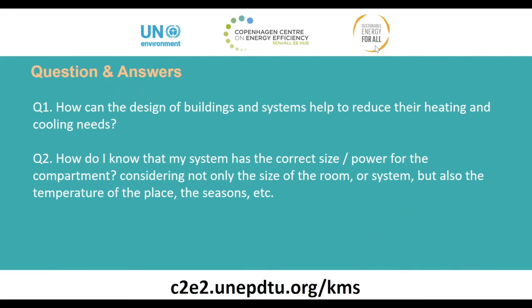Reducing or optimizing your heat loads need not necessarily be something so extreme that you have to change the designs of your buildings and systems in place. They could be as simple as segregating your heating and cooling loads. Like I have seen in many modern office buildings, where they have these coffee machines and water coolers, all placed in the conditioned area. Such appliances also add to your cooling load, because ultimately the electrical energy consumed will have to be dissipated in the form of heat in the conditioned area, right? So if you can move these appliances to a non-conditioned area, then you could probably reduce the cooling loads.